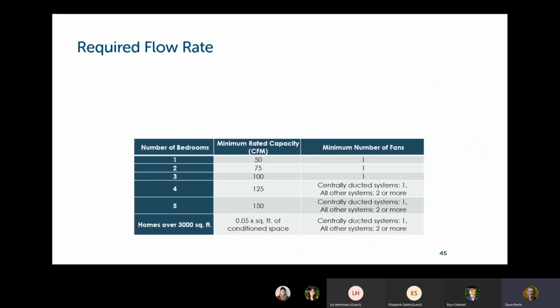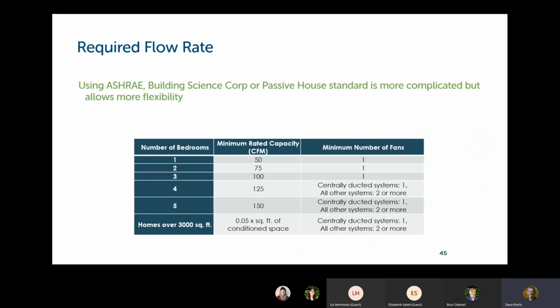So this is the required flow rate if you're using the Vermont system. If you're using ASHRAE, the Building Science Corp, or the Passive House standard, it does allow you more flexibility, and you might be able to get by with smaller fans, but it's more complicated. So your choice. If you want to use the prescriptive standard that we've had in Vermont for the last 15 years, this is what it says, and that's the CFM capacity that you have to provide based on the number of bedrooms that you have in the house. Pretty simple.